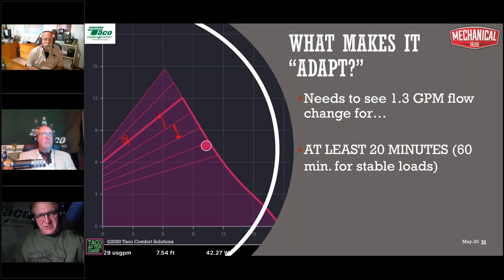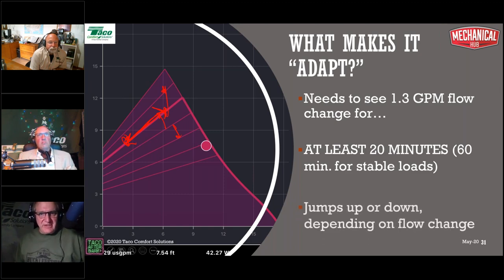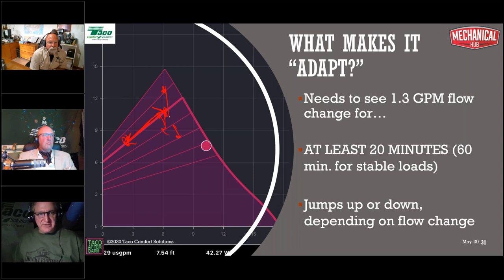Under normal circumstances, we're going to be bopping back and forth across this line as the TRVs modulate. Okay, TRVs closed, we're going to come down here. TRVs open, we're going to come up here. If there's a big change in flow, like all of a sudden I've got 1.3 gallons per minute more flow than I had before, and that goes on for a good 60 minutes, then it'll jump up one if it needs to, or jump down if it needs to. It might jump down to here, okay? So again, it's under normal operating conditions.